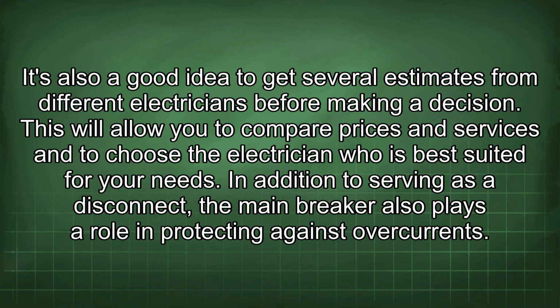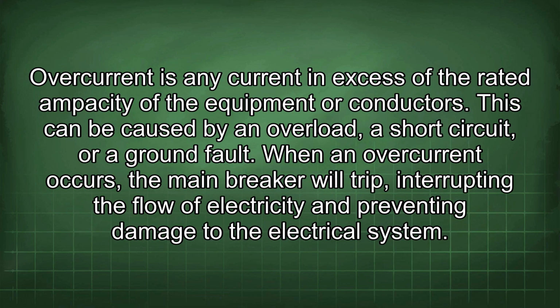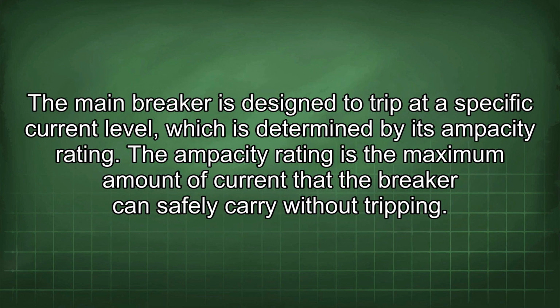In addition to serving as a disconnect, the main breaker also plays a role in protecting against overcurrents. Overcurrent is any current in excess of the rated ampacity of the equipment or conductors. This can be caused by an overload, a short circuit, or a ground fault. When an overcurrent occurs, the main breaker will trip, interrupting the flow of electricity and preventing damage to the electrical system. The main breaker is designed to trip at a specific current level, which is determined by its ampacity rating.